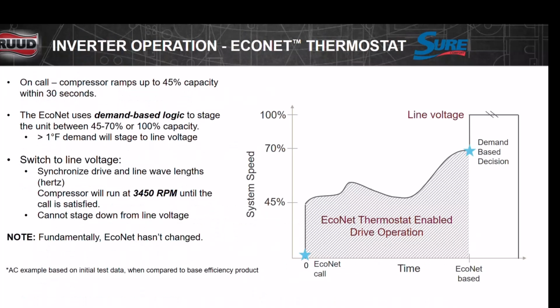This is where your difference comes in from the EcoNet controlled unit or the two-stage thermostat controlled unit. So as you can see, as the unit is running, based on demand, at 45 to 70%, we're running like a variable speed compressor. Once it gets up here to say, I've got a call for Y2, it's going to turn off the inverter and energize the contactor. You're not going to be able to notice that's happening, but it's going to. So it doesn't stop and start. No. Compressor's just going to pick up at high RPMs. It switches. Here we're running on time. I mean, it's just running, right?